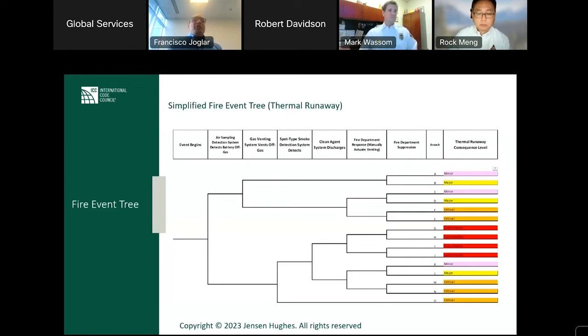I mentioned an inventory and a chronology. This is a sample one that captures what we believe, and have been doing, is the essence of the HMA, which is not a brute force list of all the potential failure modes of the system, because this is a fire and explosion study. So we look at what failures can end up in thermal runaway, and then what the consequences are, and we try to build a chronology of the event that starts with air sampling systems. Maybe we start the ventilation system.